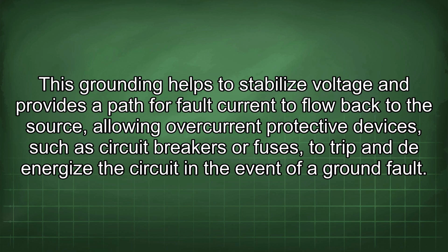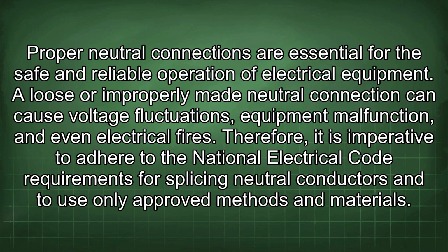This grounding helps to stabilize voltage and provides a path for fault current to flow back to the source, allowing overcurrent protective devices, such as circuit breakers or fuses, to trip and de-energize the circuit in the event of a ground fault. Proper neutral connections are essential for the safe and reliable operation of electrical equipment. A loose or improperly made neutral connection can cause voltage fluctuations, equipment malfunction, and even electrical fires. Therefore, it is imperative to adhere to the National Electrical Code requirements for splicing neutral conductors and to use only approved methods and materials.